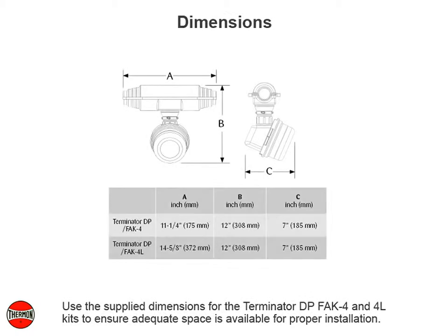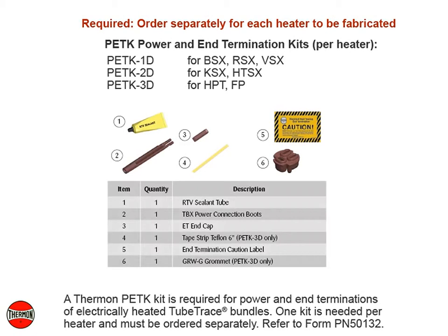Use the supplied dimensions for the Terminator DP, FAK-4, and 4L kits to ensure adequate space is available for proper installation. A Thermon PETK kit is required for power and end terminations of electrically heated tube trace bundles. One kit is needed per heater and must be ordered separately. Refer to Form PN50132.